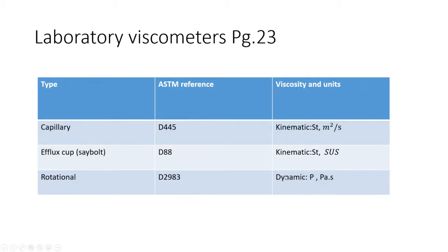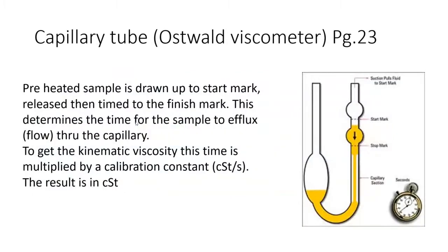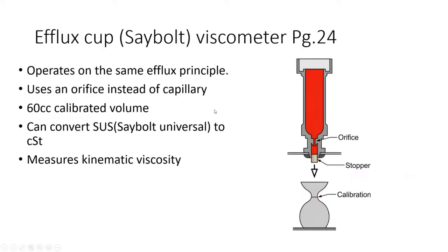The capillary tube — also called the Ostwald viscometer: preheat a sample, draw it up to a start mark, release it, and time it from the start mark to the stop mark. The time for the sample to efflux through the capillary, multiplied by a calibration constant specific to that device, gives the result in centistokes. This is just gravity and time — no force applied.